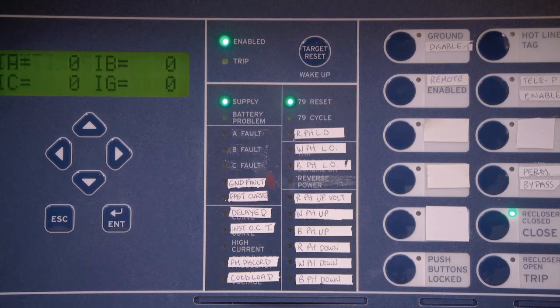79 reset. This green LED indicates that the control has reset and is ready to perform its full operation cycle. 79 cycle. This indicates when the unit is performing its operations. While switching between operations, the light will turn red. Red, white, and blue phase lockout LEDs will turn red upon lockout of these phases. When set for single-phase parameters, any combination or all of the indicator LEDs could be illuminated.